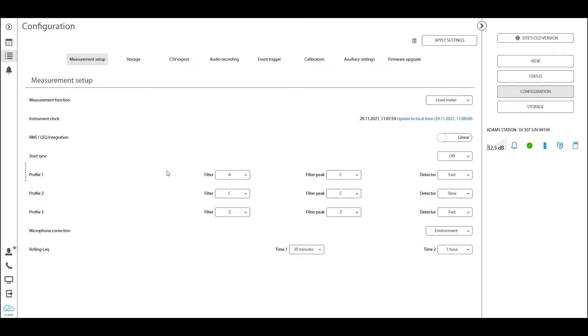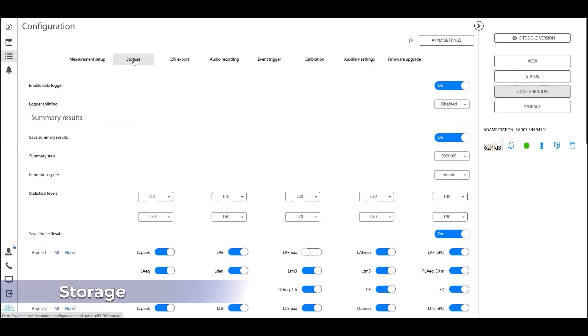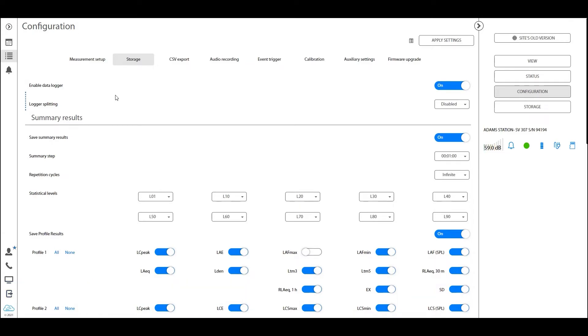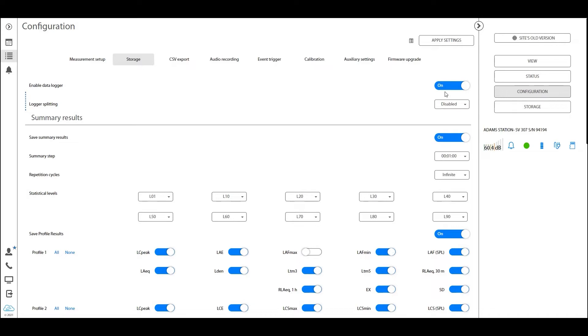Now the second most important tab after measurement setup is the storage tab. In this tab, you will be setting up your data logger, meaning that you will be defining what this station is supposed to be measuring and logging, so saving to the logger file. It's most crucial to have this on, as a station without the logger is basically just idle measuring but not saving the data.